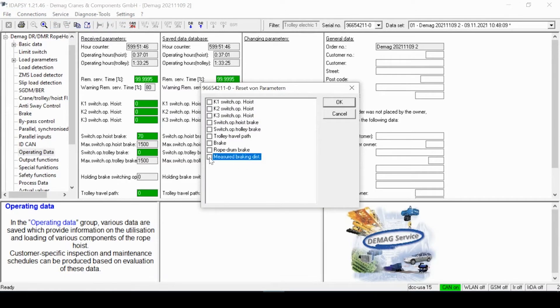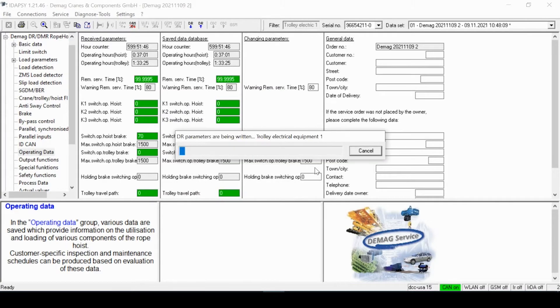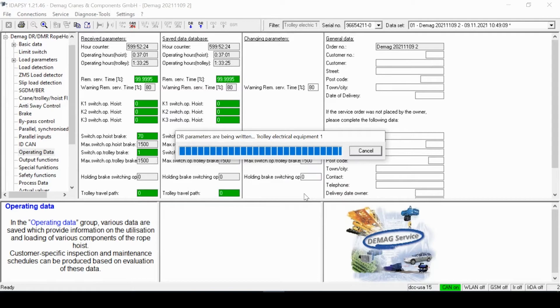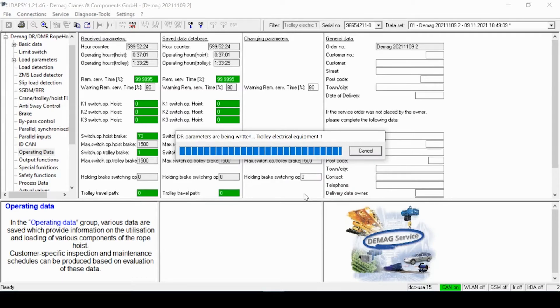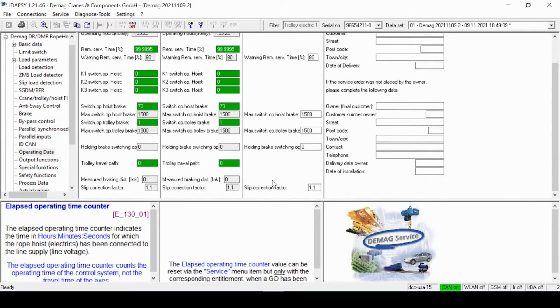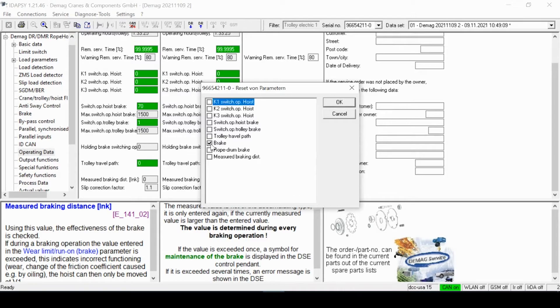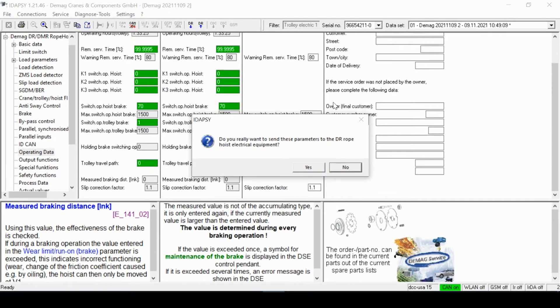If I do a brake adjustment, I would check the measured braking distance box and zero in. If I made a brake adjustment and the statistic had shown that I had totally over-traveled the amount of increments allowed in the system and lost high speed, I would put a check mark in the brake box and say okay.